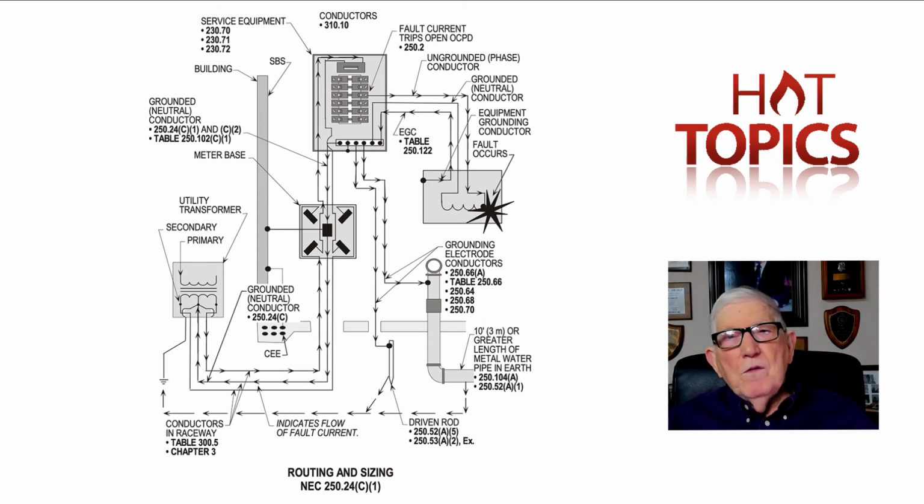But we know that it's 5 milliamp plus 1 or minus 1. So we could go up to 6 milliamps. Then it's going to open up if we should have current flowing through our bodies to ground. And that's what the definition defines there on page 36, I believe it is.